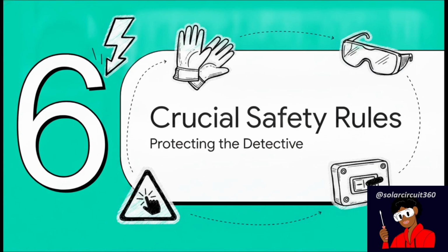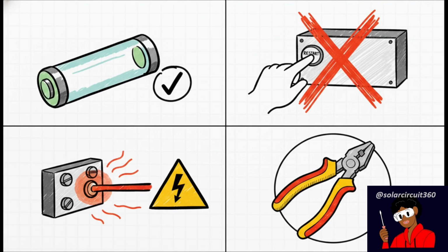Finally, Section 6, Crucial Safety Rules, Protecting the Detective. Before you go closing this case, we have to talk about some absolute non-negotiable safety rules for dealing with these high current systems. First off, never, under any circumstances, bypass your battery fuses, DC breakers, or BMS protection devices. Seriously, they are there to prevent fires, period. Next, if your inverter shuts down, stop repeatedly mashing the restart button. You're just severely stressing the unit. Oh, and if you touch a terminal and it feels hot, disconnect the power immediately. Finally, accidental short circuits from high fault currents can cause severe burns, arc flashes, and total equipment destruction. So please, always use insulated tools.